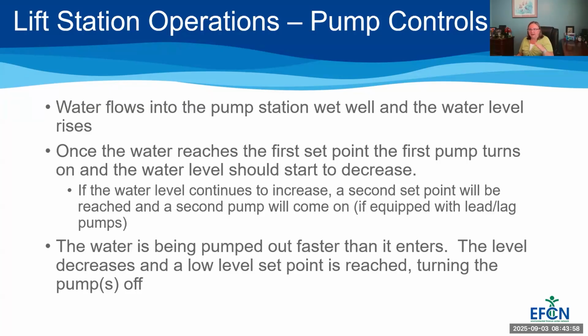Not all lift stations have that lead lag scenario. Some are just on off, but it's something to be familiar with and aware of. Once the water is being pumped out faster than it enters, the level starts to decrease and eventually reaches a low level set point, and that turns the pump, or the lead lag, both pumps turn off at the same time. They can be set in different ways, but this is kind of a general operation of how the lift station should work.